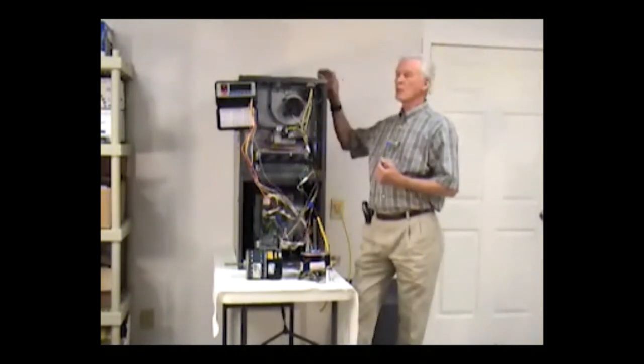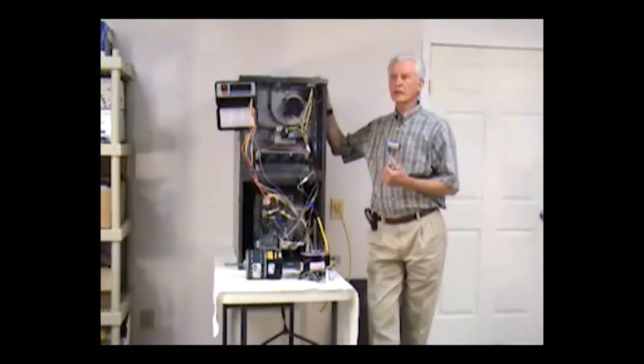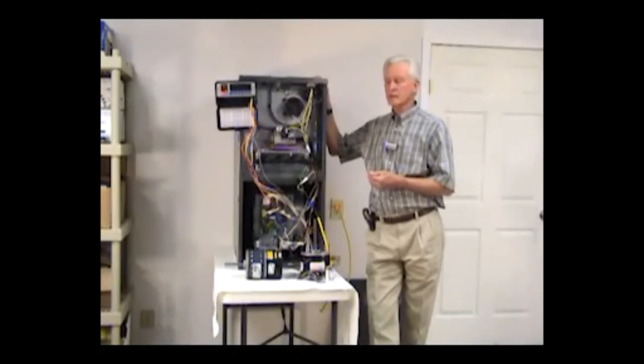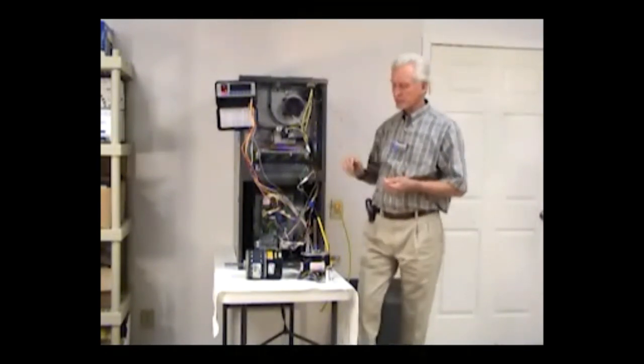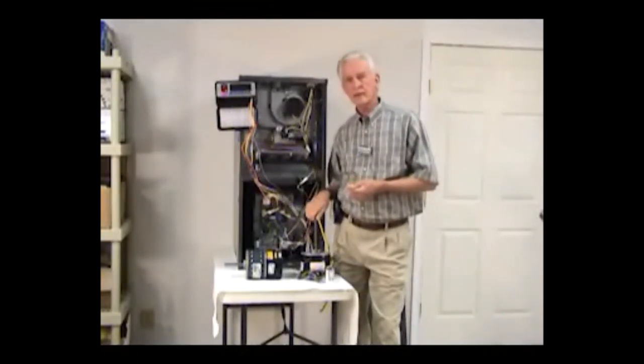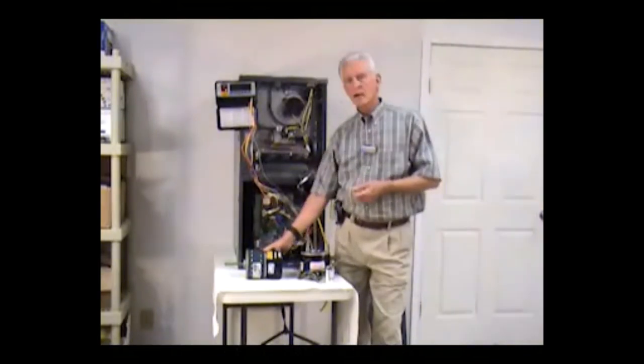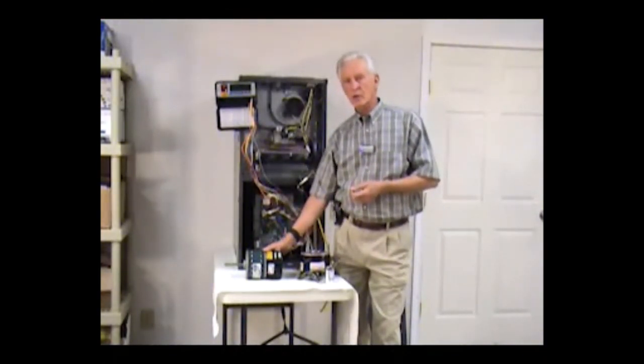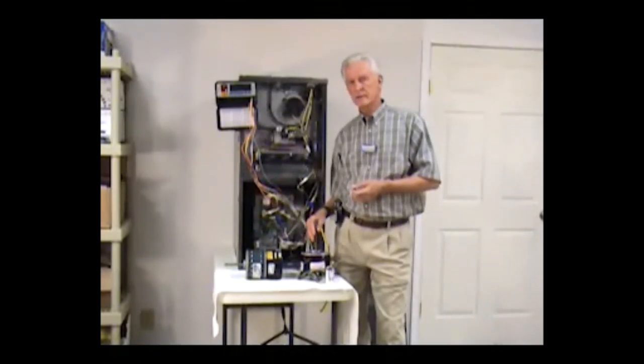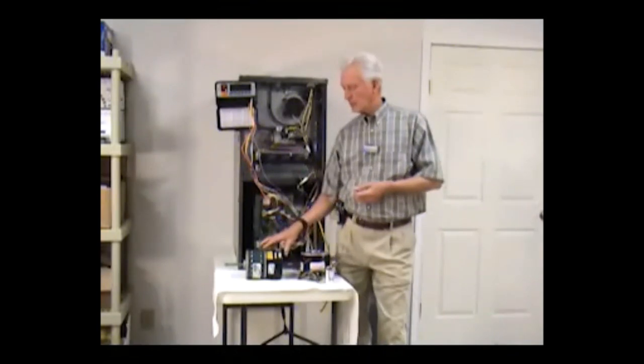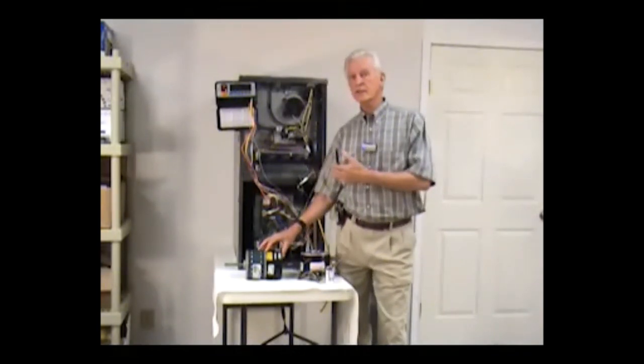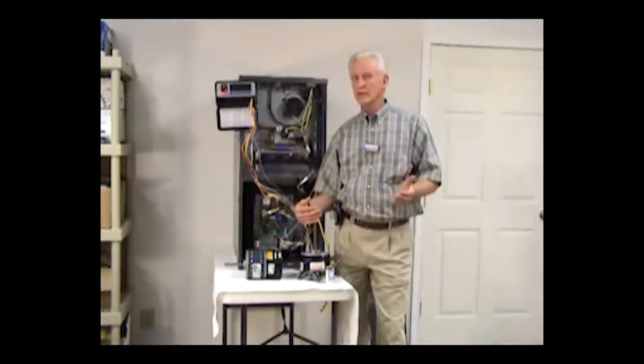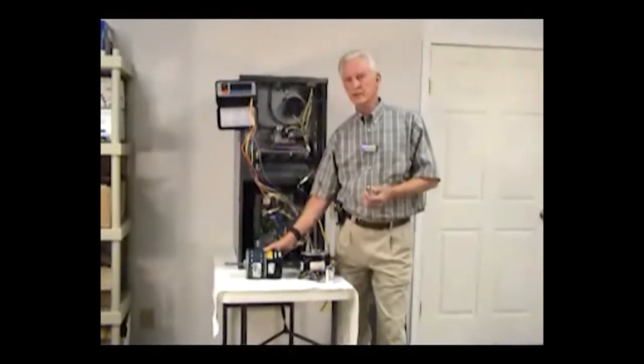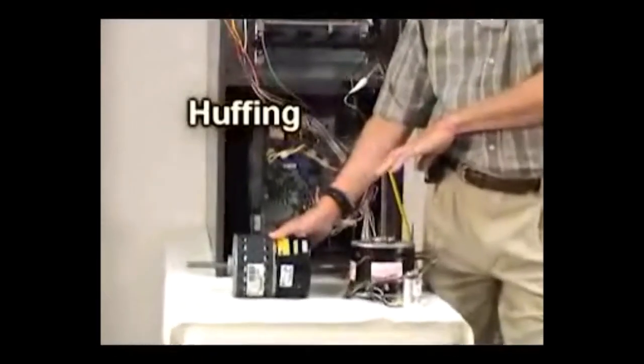If we have a somewhat restrictive duct system, although we do not want to use this motor to overcome external static pressures because of poor duct systems, it's best to have a very free duct system on your unit if possible. However, they will overcome those external static pressures by a greater margin than split capacitor motors will. As the statics go up, our amperage draws go up. That's a little vice versa of what we had here. It's the other side of the coin, if you will. So from an efficiency standpoint, if we're in higher static range, the motor becomes less efficient. If we're in lower external static ranges, then the motor is very, very efficient in comparison to any of our split capacitor motors.